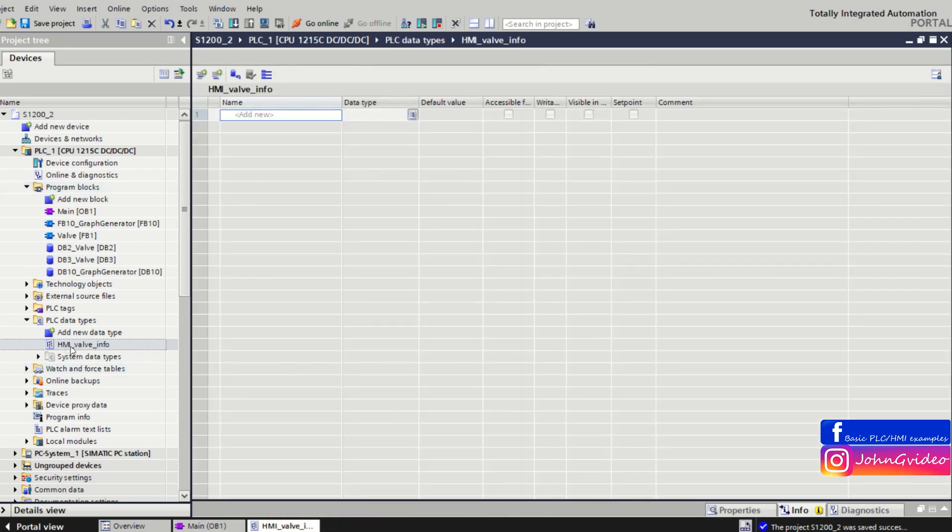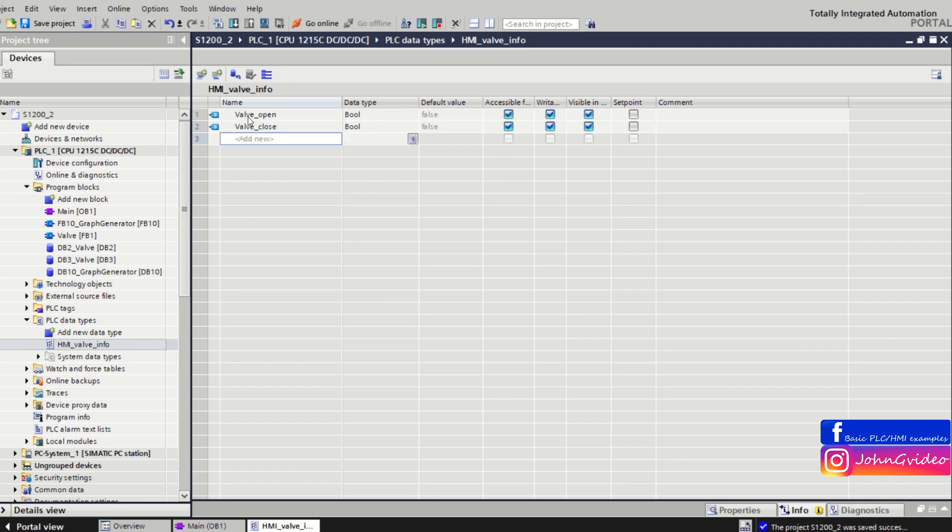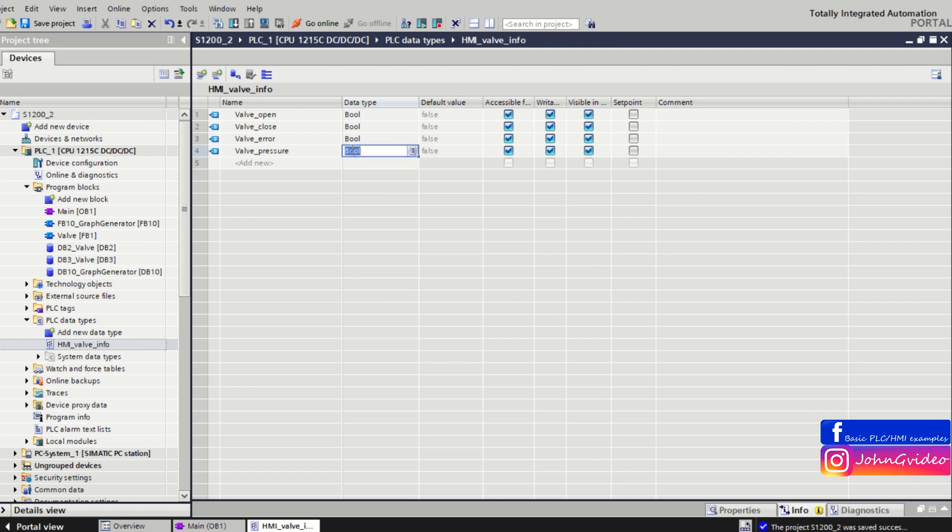We have created the HMI valve info UDT data type. For example, in this user defined type we use variable valve is open for HMI information, next valve close, then valve error, and for example valve pressure as real data type.